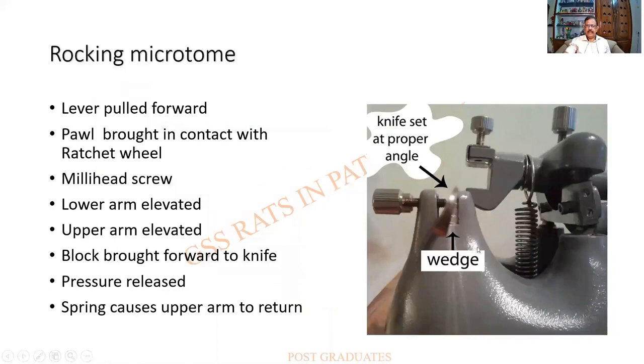At higher magnification, the knife holder is visible and there is a block holder. The block moves against the fixed knife; the lever is pulled forward and brought in contact with the ratchet wheel. There is a micrometer screw; the upper arm and lower arm allow the block to move towards the knife, and when pressure is released the spring causes the upper arm to return.